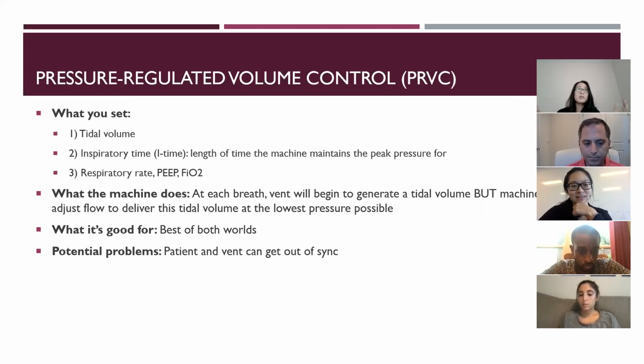Because as I mentioned with volume, you're kind of worried about delivering a tidal volume and generating too high of pressures. In this mode, the machine will deliver that tidal volume at the lowest possible pressure for you. So you are setting the tidal volume, the inspiratory time, respiratory rate, PEEP, FiO2, and the machine will do it, but it will also keep in mind that it doesn't want to just do it at any pressure possible. It's going to do it at the lowest one. So you avoid barotrauma. What it's good for, best of both worlds.